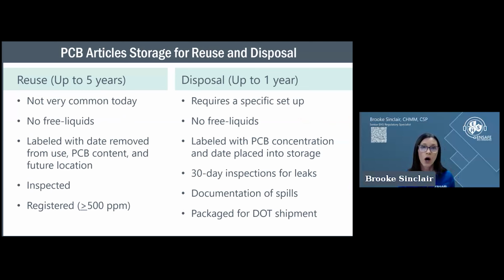Once it's a PCB article—that's a term in 40 CFR 761 meaning any kind of electrical equipment, a generic term covering transformers, switches, voltage regulators, capacitors, whatever—those are all articles. You have options for how you store them: store for reuse versus store for disposal. If you're planning to reuse that piece of equipment, unless it's a very special piece, I'd typically recommend not doing that. But there is some substation-level and network-level equipment that's very specific and costly, and you might need a spare—that's where I see a lot of this coming in for spares.